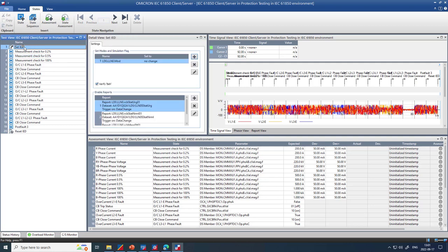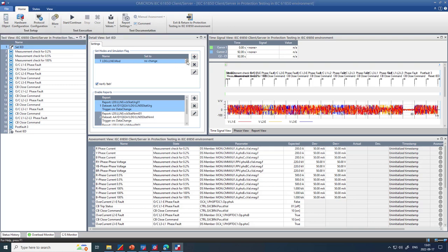And most importantly, after importing the IED, we need to also manage here no change in case you really don't need to change anything. If you want to change the mode of the IED under different situations, to test mode, and the real environment or test environment to check it, that's also possible, flexible, you can manage it. And enabling the reports at this level is very important. We need to pick the reference that will be used in different states. Those report control block instances need to be occupied before we add the different test states.